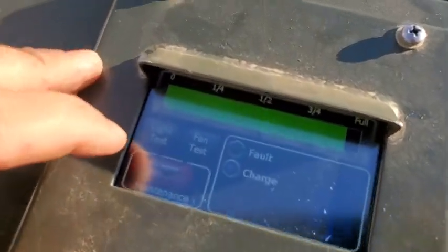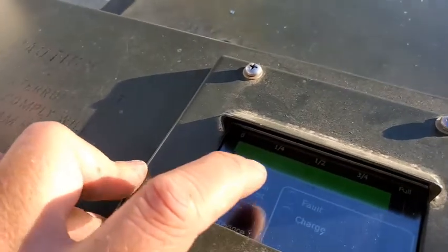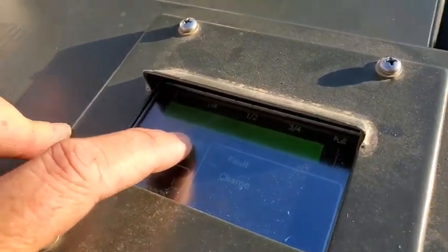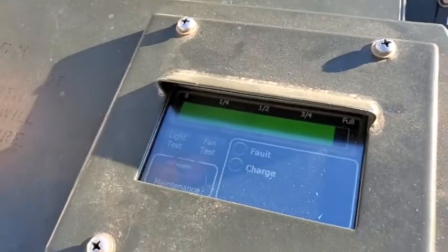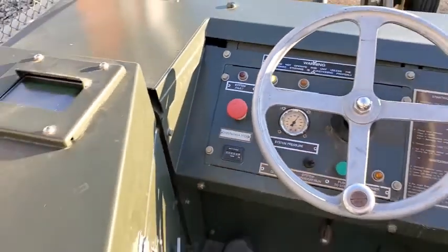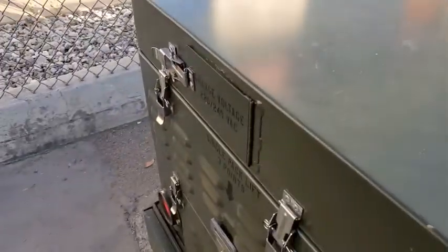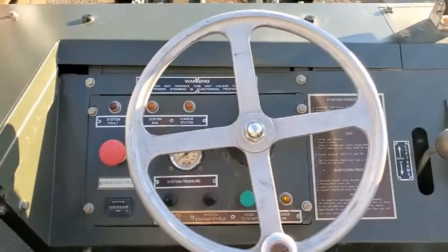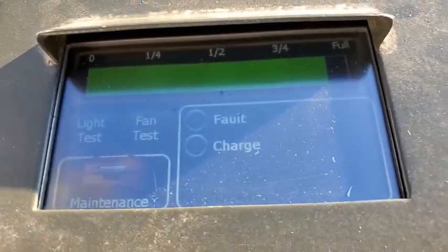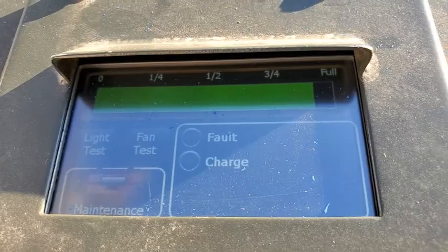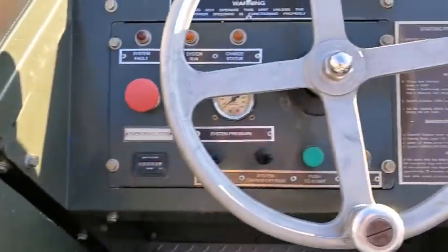We've also got a fan test button here to make sure that the two cooling fans located here and here are operating. So press that button and feel for air coming out of both of those vents. I'm going to go ahead and turn off the hydraulic motor. The system is still on, as you can see. I just stopped the pump temporarily without turning everything off.